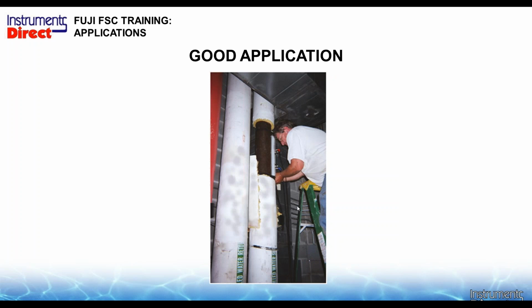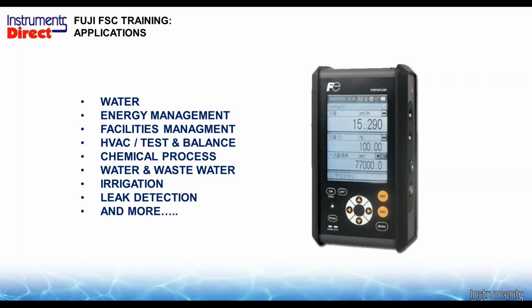Even a good application may require some attention. You may have to use a ladder, you may have to use scaffolding, you may have to remove insulation off the pipe wall. So with good applications, you may still have to work hard to get it to work for your particular application. So where does this technology actually work? The ultrasonic transit time technology works in applications that have no suspended solids. The ultrasonic flow meter that requires suspended solids is an ultrasonic Doppler flow meter. Different can of worms altogether. Doppler flow meters are designed for applications with lots of suspended solids.